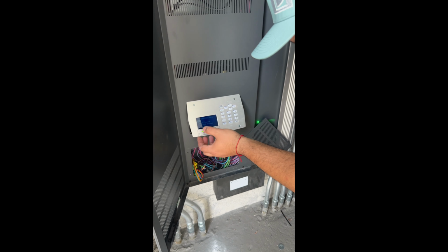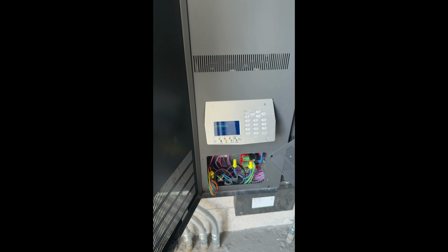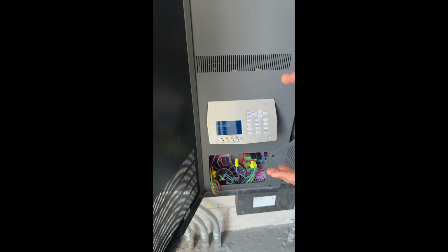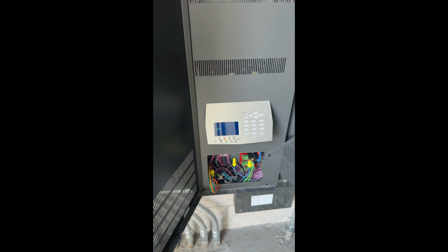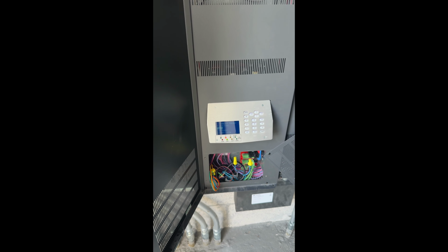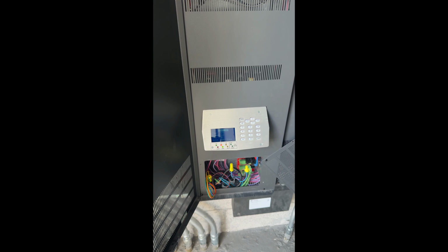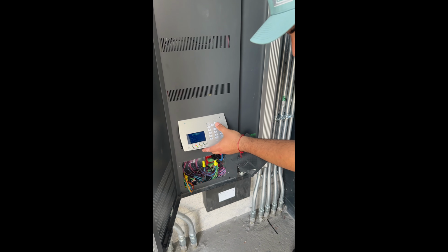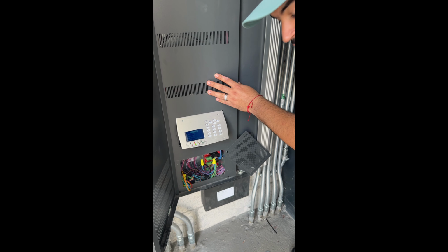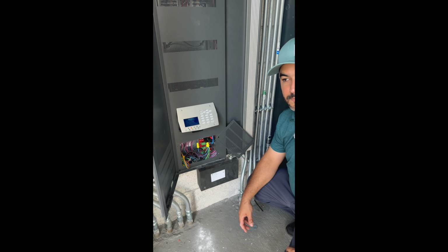For time events, in the same operation menu, we go to time clocks manager, and on time and date is where we set the lighting control panel to the precise time and date. On events is where we create new time events, meaning turning on and off individual areas at a specific time. As I mentioned, we only have 2 events: turning on 10 minutes before sunset, and turning off 10 minutes after sunrise. Since the lighting control panel is an astronomical time clock, it will self-adjust every time there is a daylight saving.